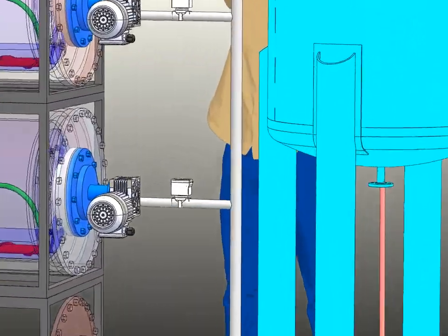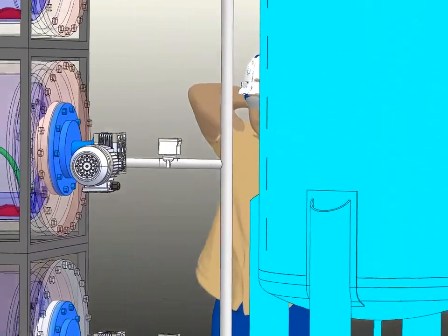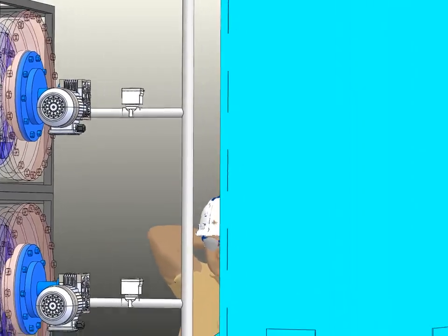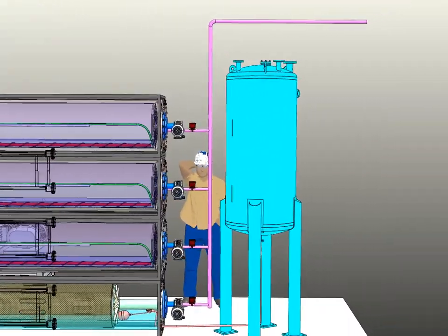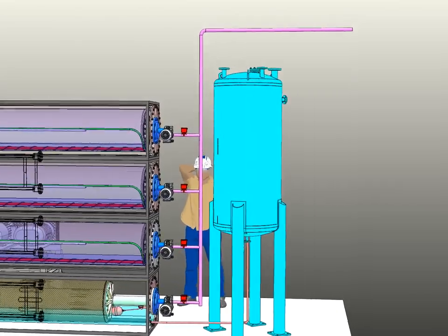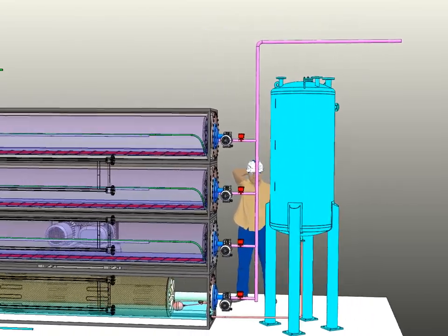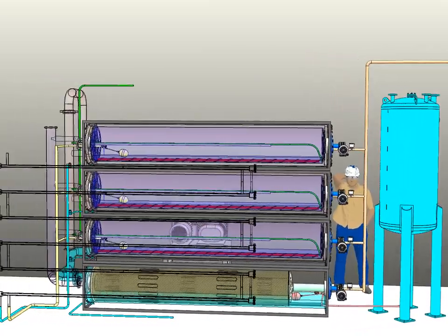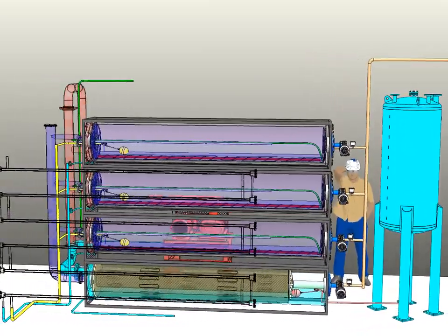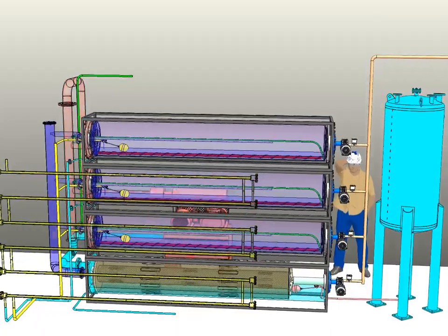During condensation and evaporation, heat transfer is very efficient, but the presence of non-condensable gases can drastically reduce that heat transfer during condensation. To prevent this phenomenon, it is possible to periodically discharge to ventilation the gas-vapor mixture when the electromagnetic valves are opened for a short time.